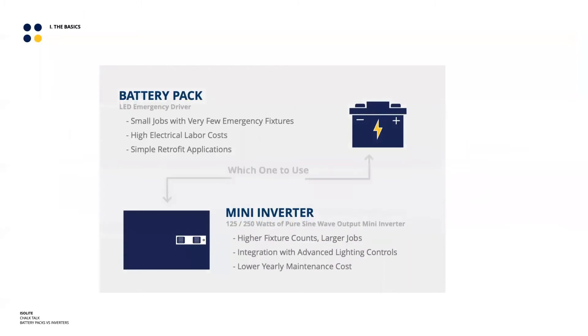The brass tacks: we're trying to decide where it makes sense to use LED emergency drivers — battery packs — versus mini inverters. You'll be better off with a battery pack if you have a very small job with very few emergency fixtures, around three, four, or five fixtures; if you have really high electrical labor costs due to union or jurisdiction reasons; if you want to avoid the inverter's wiring requirements; or in a retrofit scenario with existing fluorescent inverters.